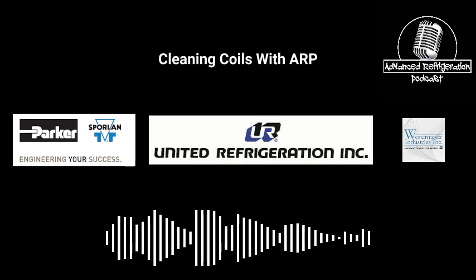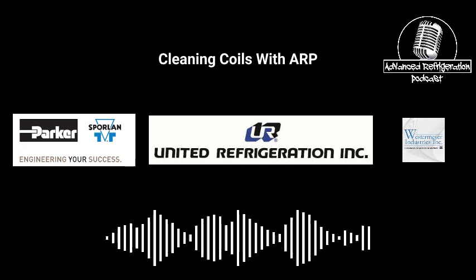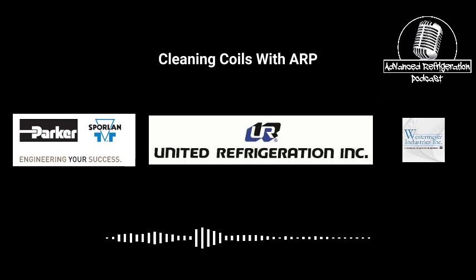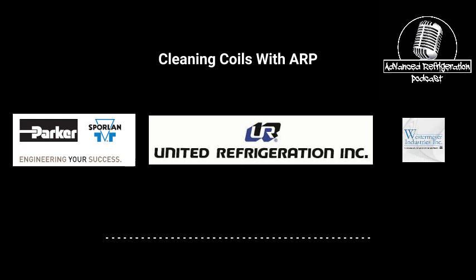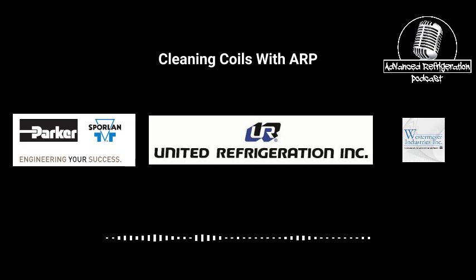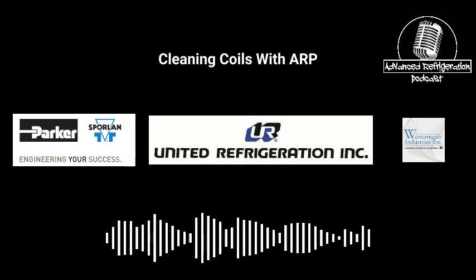Check the TDs on condensers, and make sure the condensers are blowing straight up, or like Heatcraft units are blowing straight back. If you have Heatcraft units, like little unit coolers, and the condensers are blowing up the sides and not blowing straight back at you, that thing's plugged. So you need to clean that thing. And on those smaller condensers, to do it right, you need to take all the skins off. The condenser fan motors need to be unbolted, and you need to clean it from the inside out to push all that debris out of there. And if nobody's done that in a long time, you need to either hit it with a power washer or use chemical.